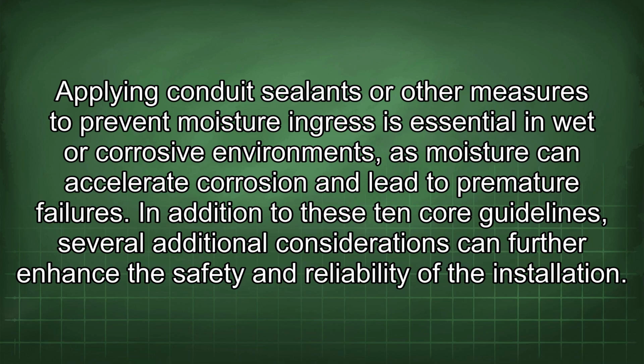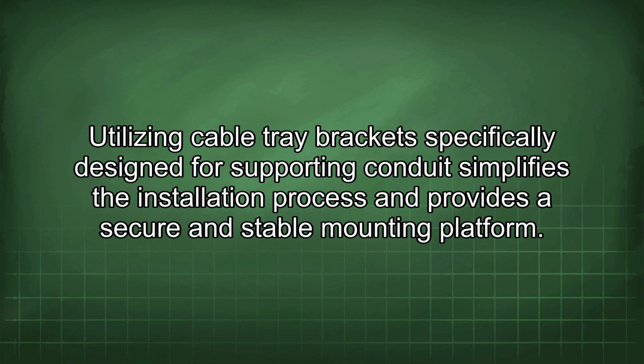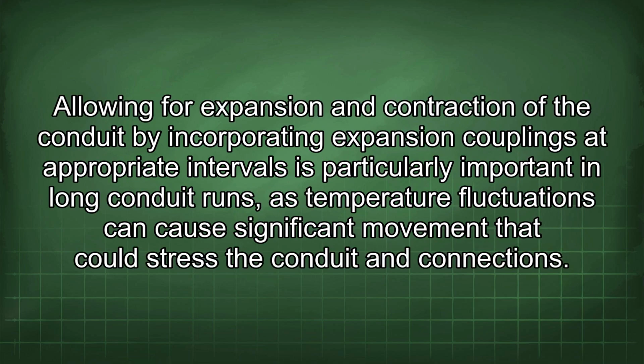In addition to these 10 core guidelines, several additional considerations can further enhance the safety and reliability of the installation. Utilizing cable tray brackets specifically designed for supporting conduits simplifies the installation process and provides a secure and stable mounting platform. Allowing for expansion and contraction of the conduit by incorporating expansion couplings at appropriate intervals is particularly important in long conduit runs, as temperature fluctuations can cause significant movement that could stress the conduit and connections.